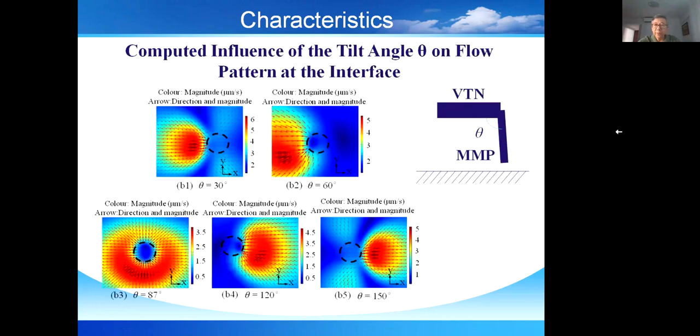Also, we found that the angle made by the vibration transmission needle and the microprobe can affect the concentration effect. The angle must be around 90 degrees to get a strong enough concentration effect.